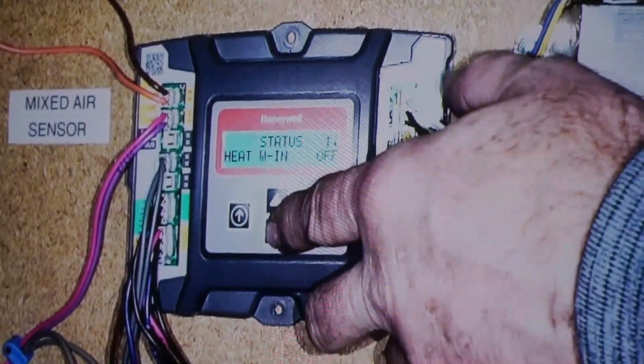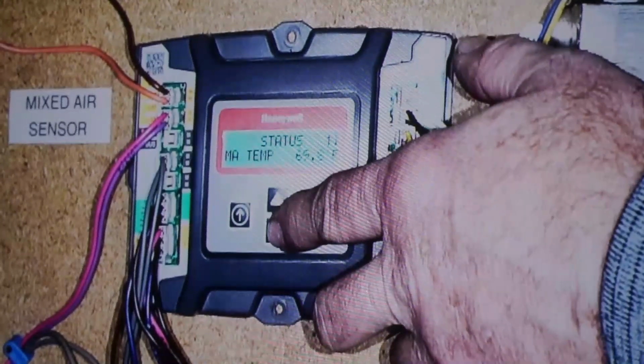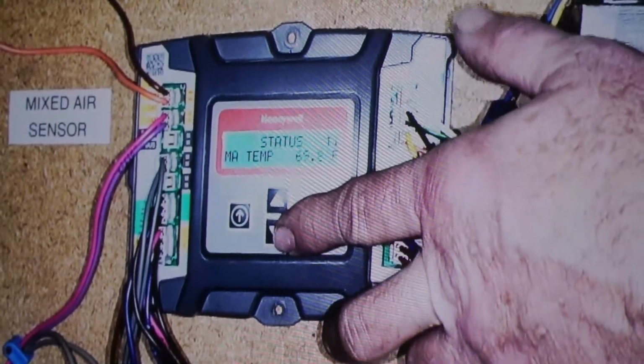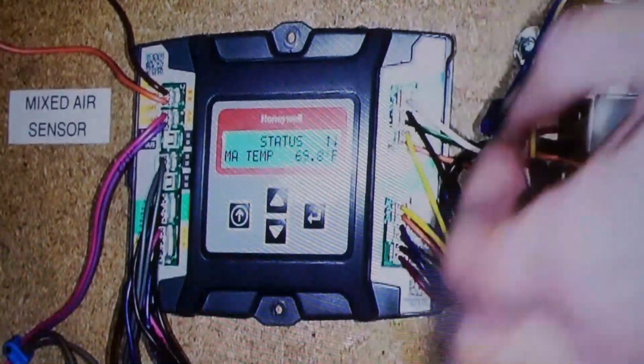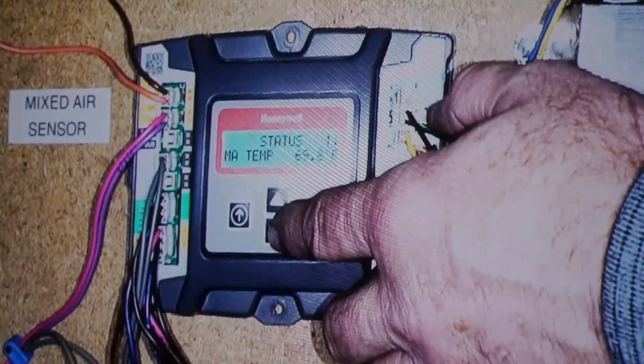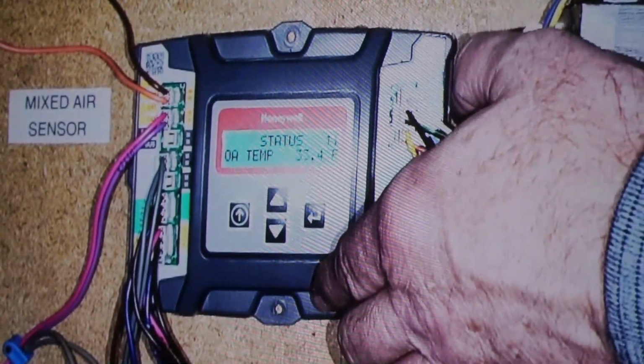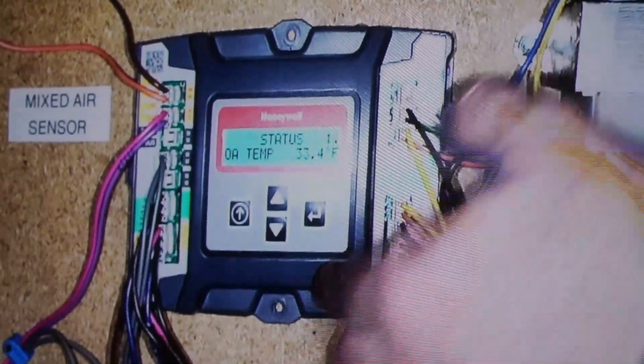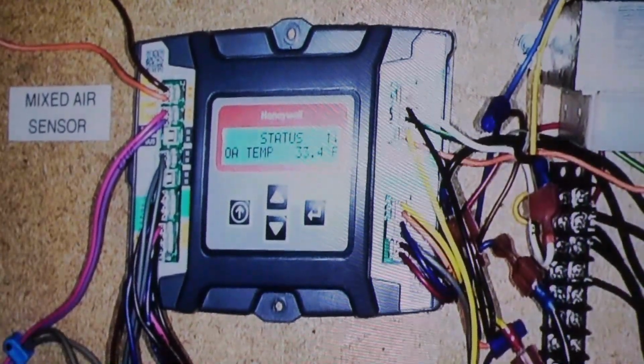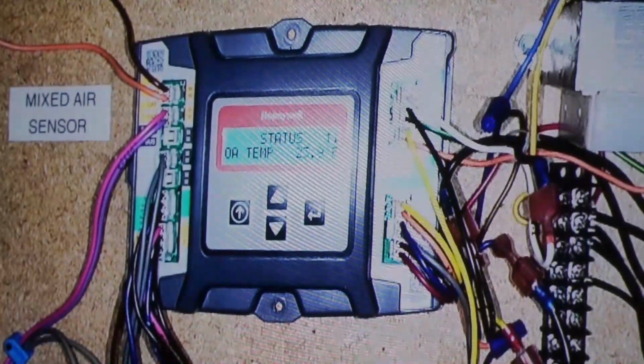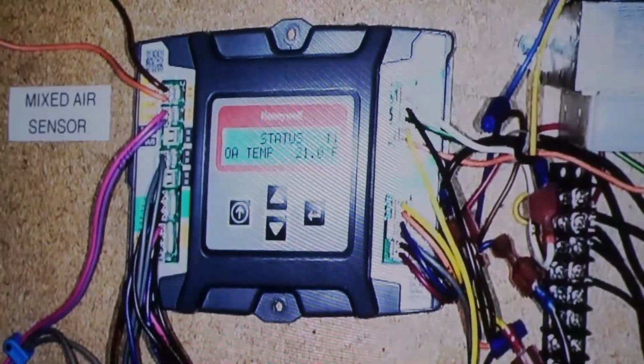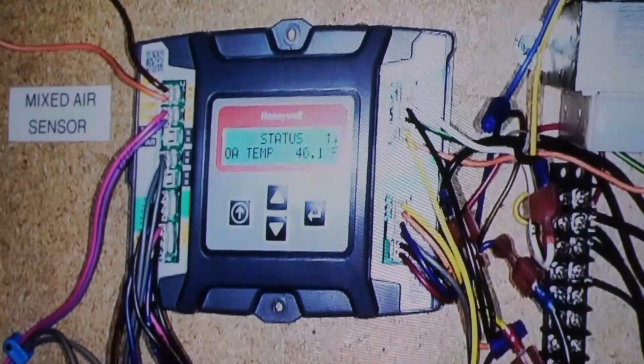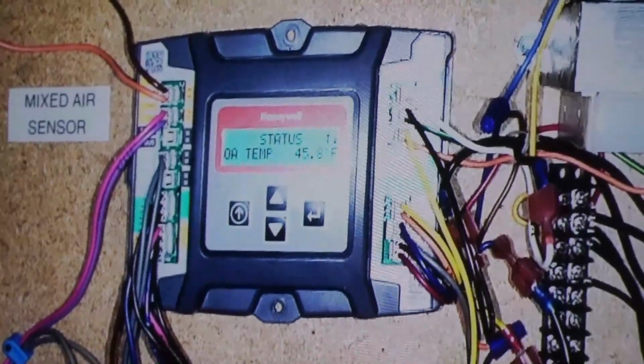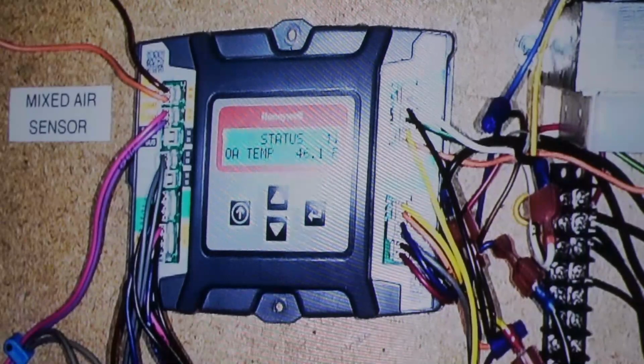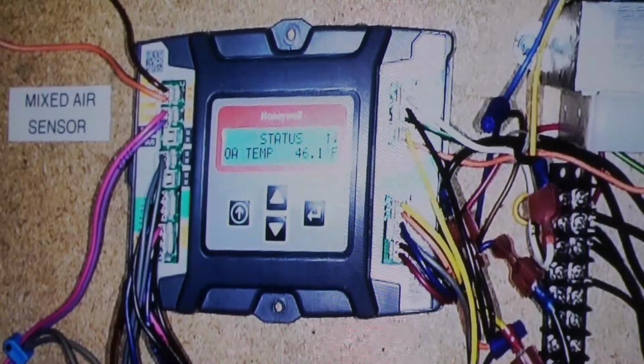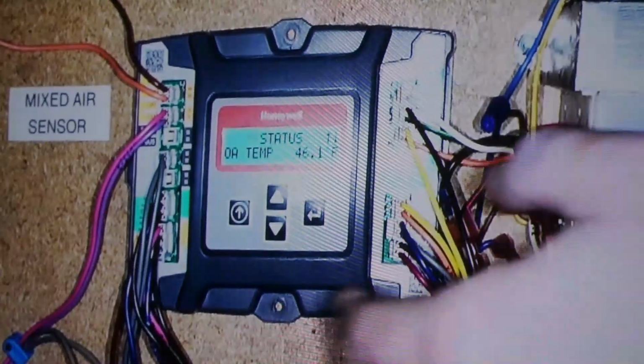Do I have a heat call? Nope. My mixed air temperature is 69.8 degrees, and that's an actual sensor there. Feels warmer, but that's what it is. And my outside temperature is 33.4, and that's on this guy here, so if I change the resistance, it's getting colder, and then it's getting warmer. So, 10,000 ohm thermistor in there, it's reversed. RTD, whatever that's called.